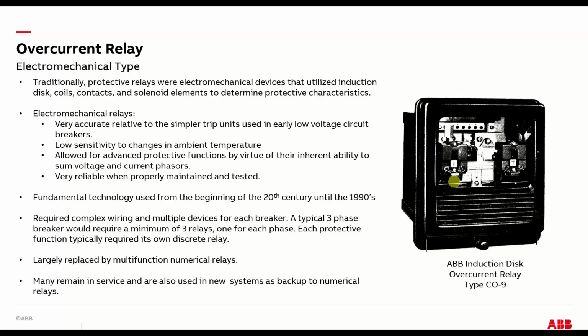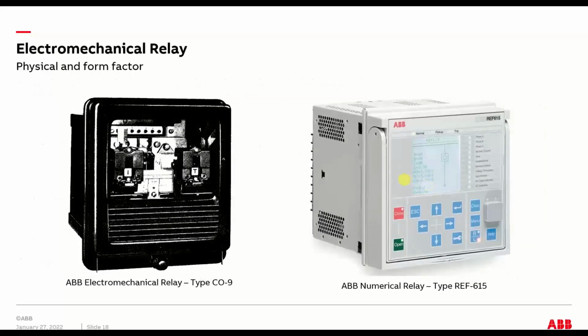Now that's all changed. And current day, in my mind, there's no real difference in the accuracy you can get between a low voltage circuit breaker with an electronic trip unit and a high-end relay. So they started out in two different directions for two different applications, but now they're very much overlapped in what you can do with them. But this last point's kind of good. I know there's a lot of these that still are in service, so I expect that some of you are going to get applications where you're going to put a new system on where you're going to utilize multifunction relays, but you've got to coordinate it with an old induction disk. So hopefully this will help you out, because these have been around for a long time and they're not going anywhere.